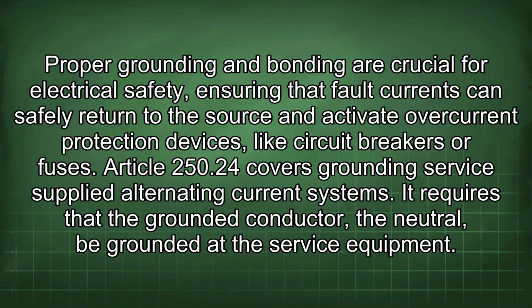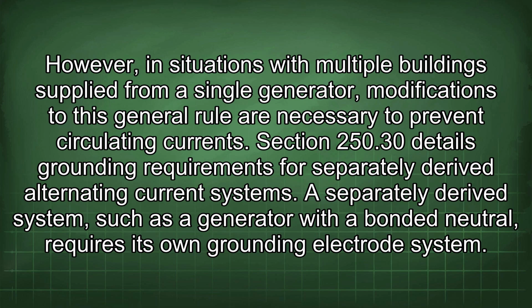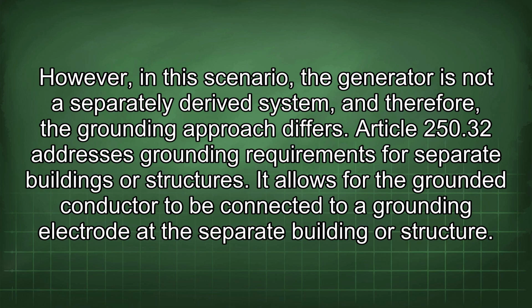Article 250.24 covers grounding service supplied alternating current systems. It requires that the grounded conductor, the neutral, be grounded at the service equipment. However, in situations with multiple buildings supplied from a single generator, modifications to this general rule are necessary to prevent circulating currents. Section 250.30 details grounding requirements for separately derived alternating current systems. A separately derived system, such as a generator with a bonded neutral, requires its own grounding electrode system. However, in this scenario, the generator is not a separately derived system, and therefore the grounding approach differs.